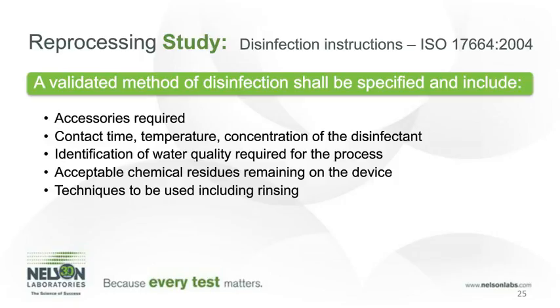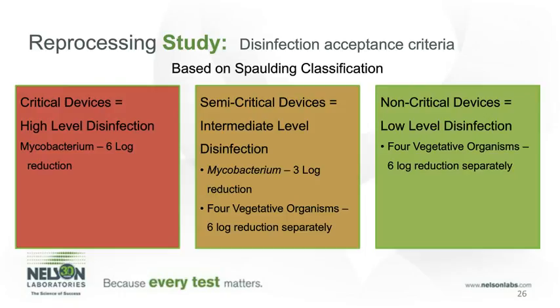The disinfection acceptance criteria is based on Spaulding classification. Critical devices must go through a high-level disinfection, and the acceptance criteria is a 6-log reduction of a mycobacterium species. For semi-critical devices, those devices will go through an intermediate level disinfection, and the acceptance criteria of this disinfection includes a 3-log reduction of a mycobacterium species and a 6-log reduction separately of each of 4 vegetative organisms. And these organisms include Escherichia coli, Klebsiella pneumoniae, Staphylococcus aureus, and Pseudomonas aeruginosa. Non-critical devices need to go through a low-level disinfection, and the acceptance criteria is also 6-log reductions separately of the 4 vegetative organisms that I just mentioned.